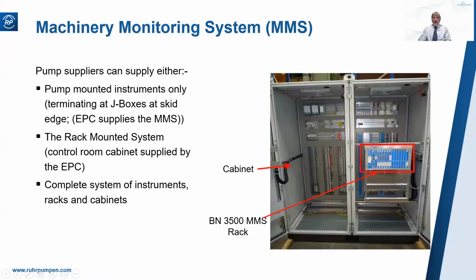Sometimes the pump supplier will supply the racks for installation in the cabinets being supplied by the EPC. The chances are that you've got several pumps from several manufacturers all going into the same cabinets. The crucial thing, if you're going to ask the pump vendors to supply an MMS, is to clearly specify what you want. Don't just ask the pump vendor to supply a suitable MMS. You don't know what you'll be getting.